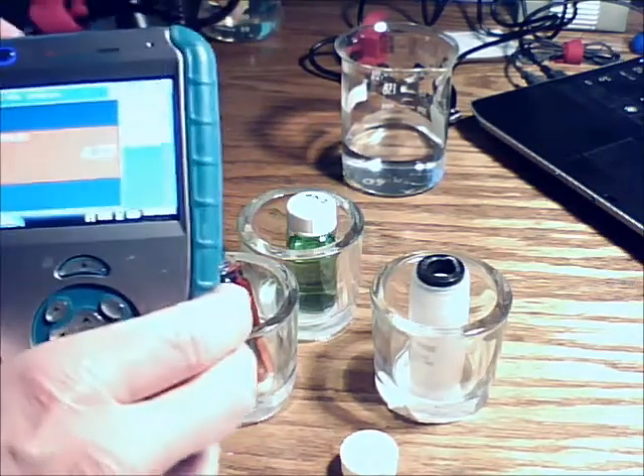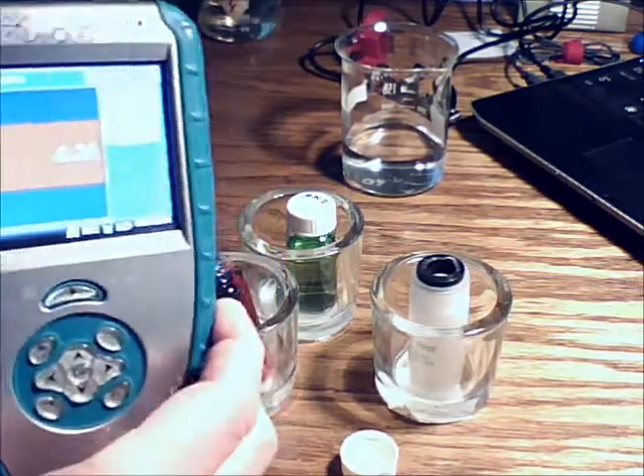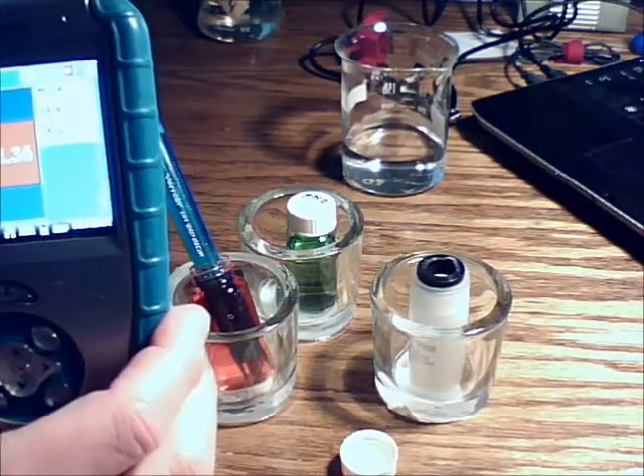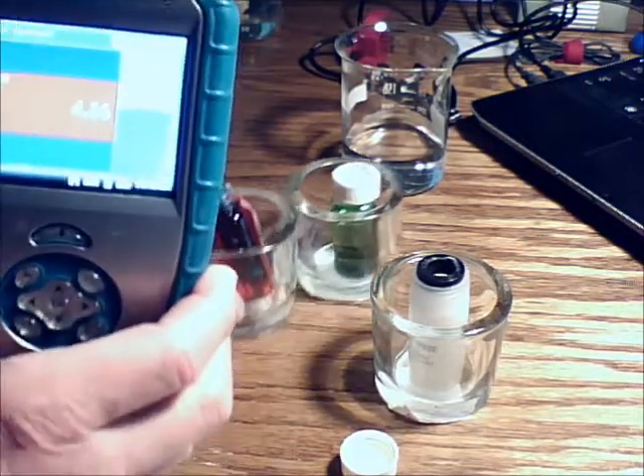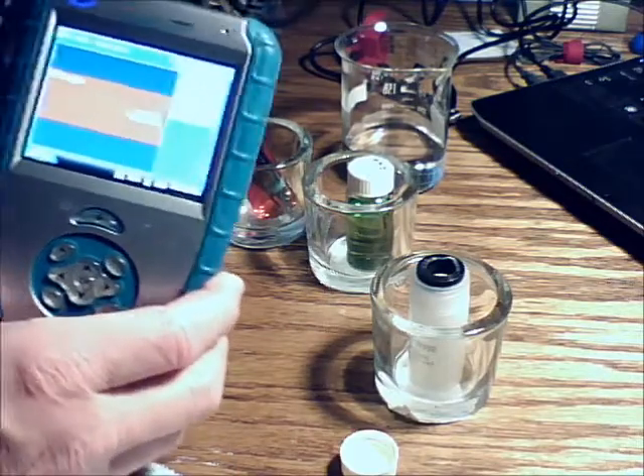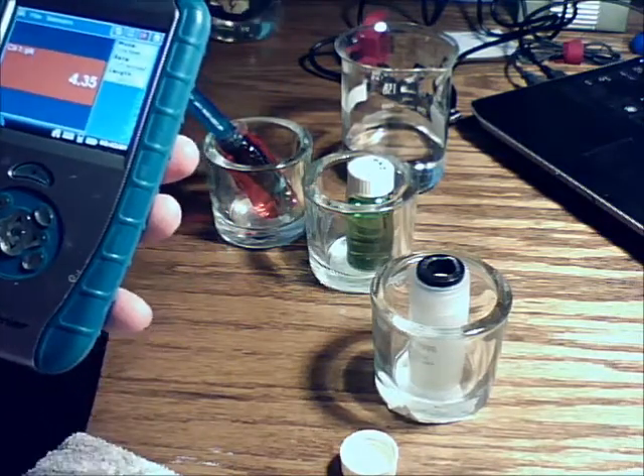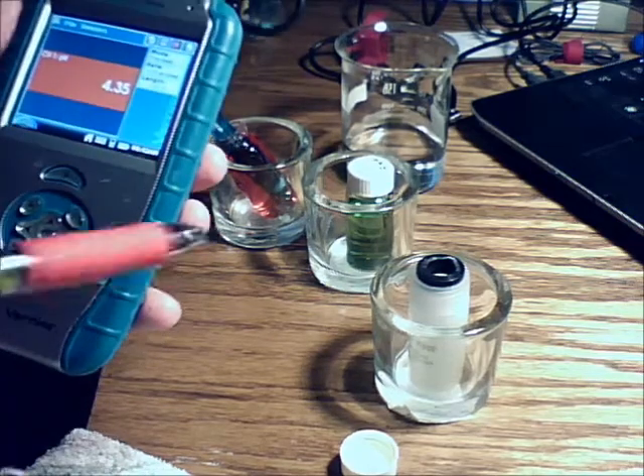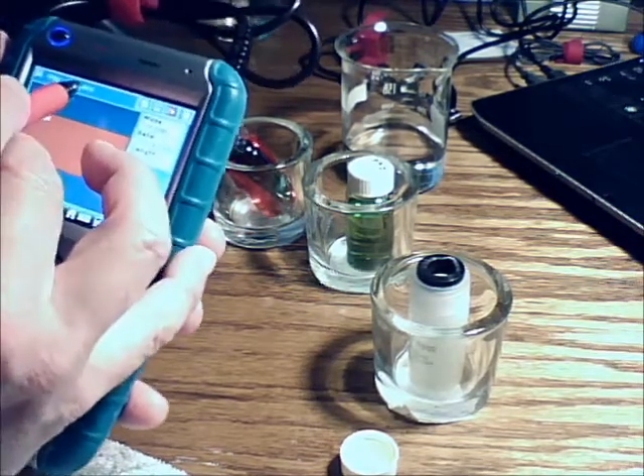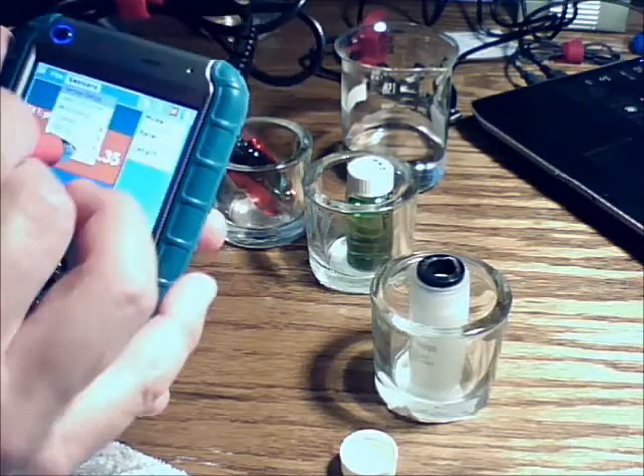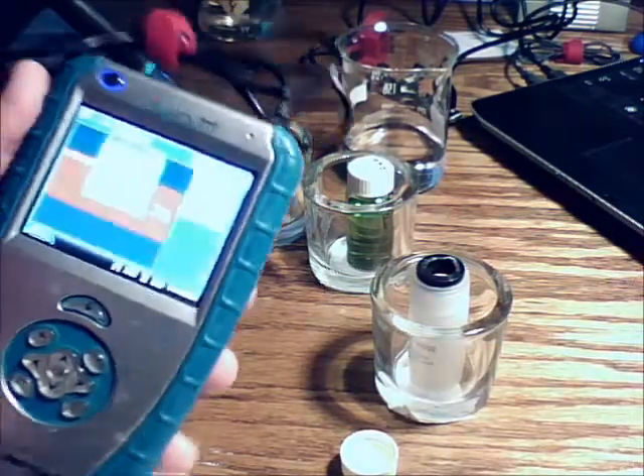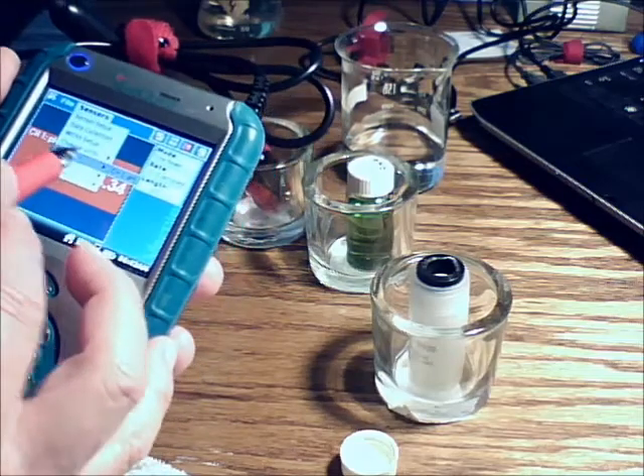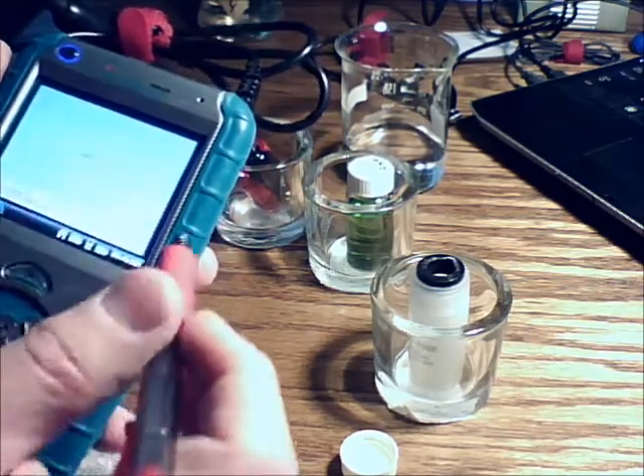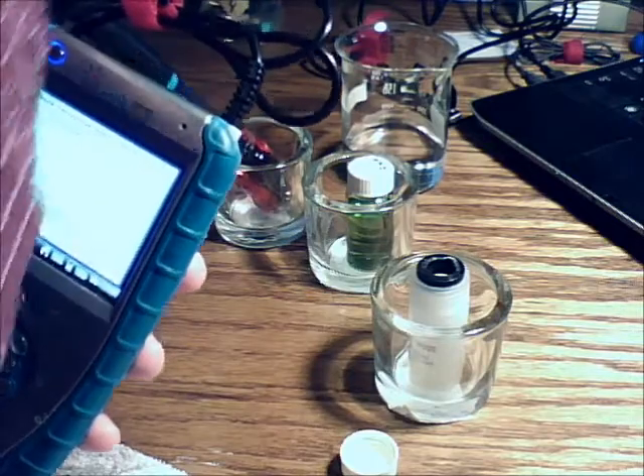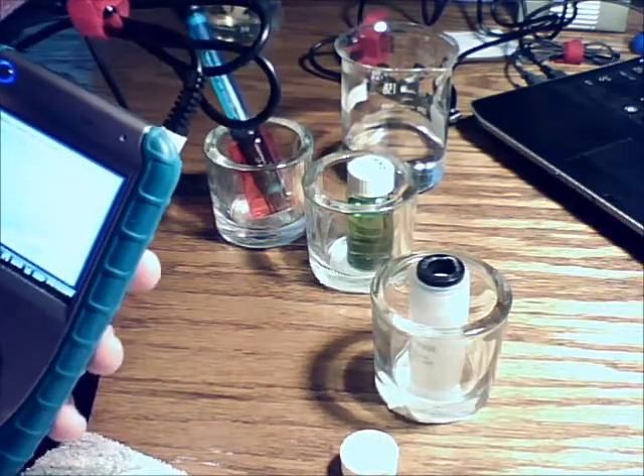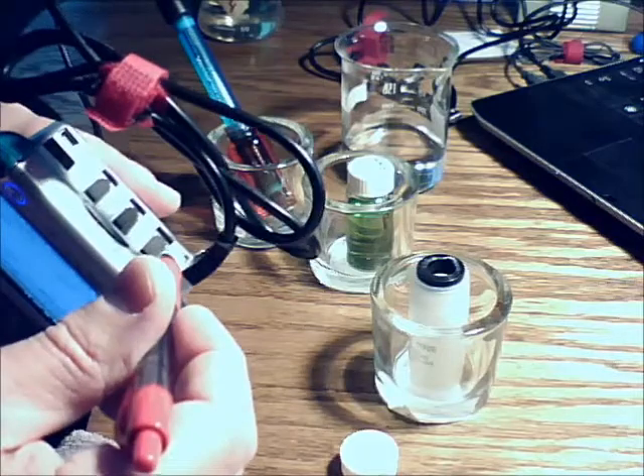Pull it around here so you can see it a little bit better. And we're going to calibrate. So each of these LabQuests are supposed to have a little probe in the end of it, and I don't happen to have the one. This is the one I borrowed from somebody. They don't have theirs in there. So I'm going to do it with the tip of a pen that's not actually functioning. What I want to do is go to Sensors, if it'll do it. There we go. And Calibrate. Can you see Calibrate on there? Maybe not, but it says Calibrate. And then pH, and it says pH 1, and that doesn't mean the pH is 1. It means the pH is in the channel 1 up here at the top.